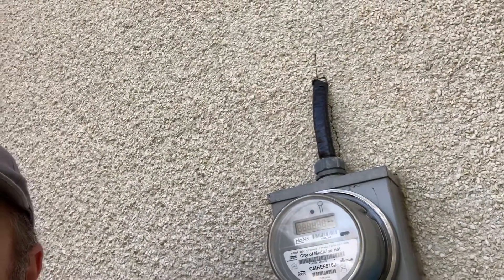Today on this home inspection I've discovered some overhead service conductors that have been repaired. You can see here that the homeowner has got some tape on the electrical service wires, and that probably means that the cloth insulation on the electrical service conductors was starting to break down and it was exposing the conductors underneath. This is a fire hazard and electrocution hazard.